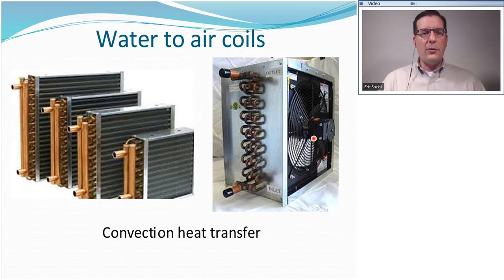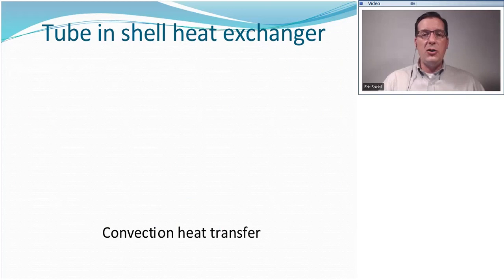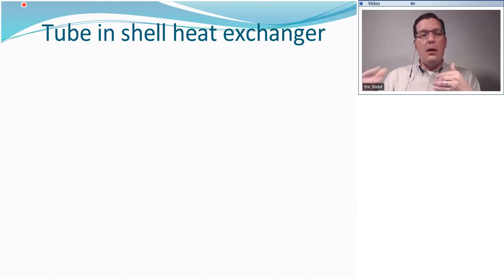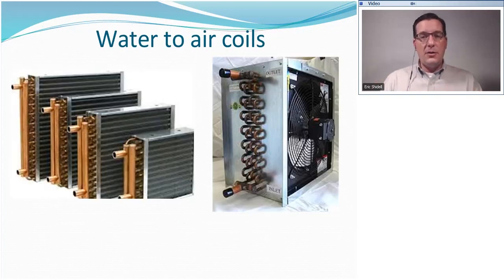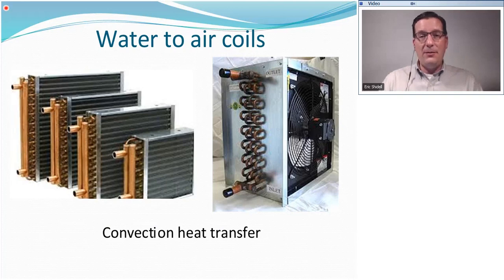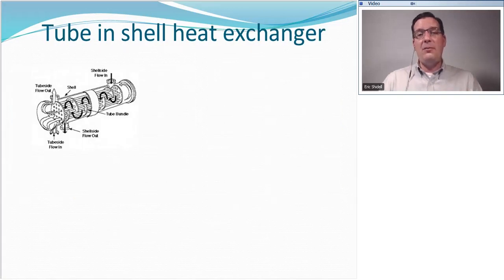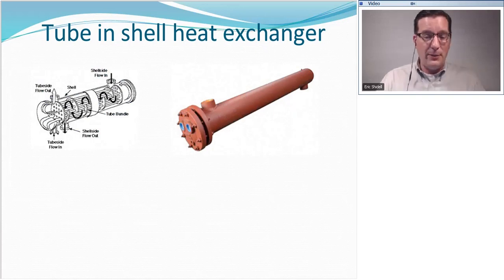Another form of heat exchanger we're going to find is called the tube-in-shell heat exchanger. Oh, by the way, these are also mirror images of the copper fin tube boiler. Tube and shell heat exchangers are mirror images of the tube and shell boiler, or the shell and tube boiler, the fire tube boiler. But now what we have is one water stream flowing through the tubes and another water stream flowing through the shell. This allows us to exchange heat from one source of water into another source of water.